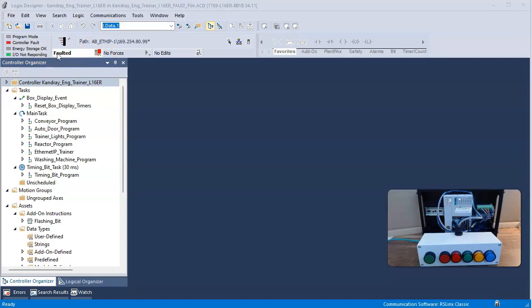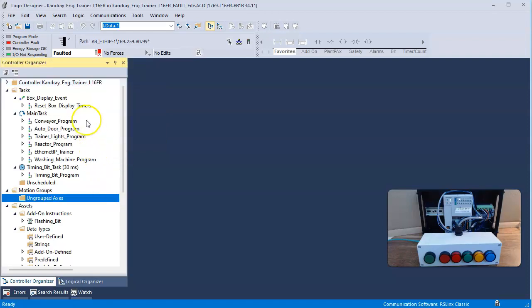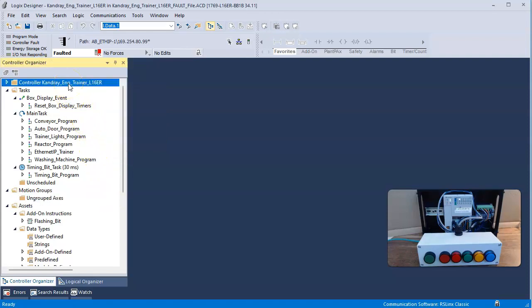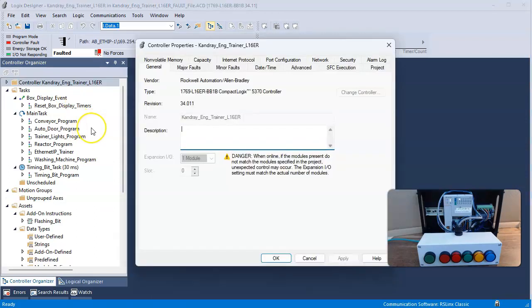I could at this point open this up and attempt to clear the fault, but before I do that, it may be of better interest to find out what the fault is. So I come down here to controller properties and I either hit Alt+Enter or right mouse click and go to properties, and I'm going to check the fault.